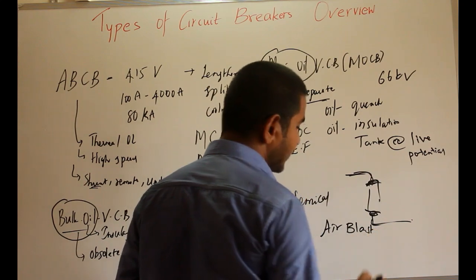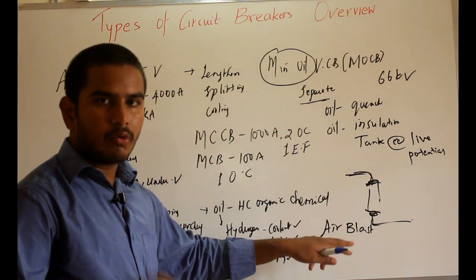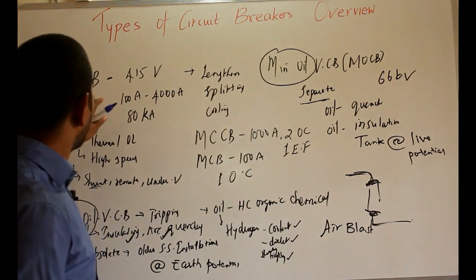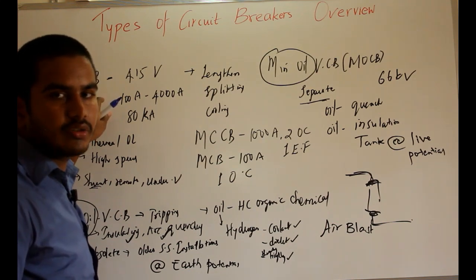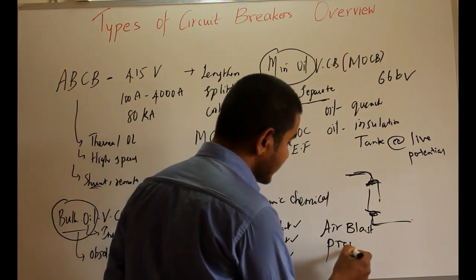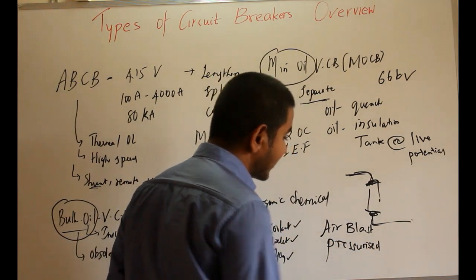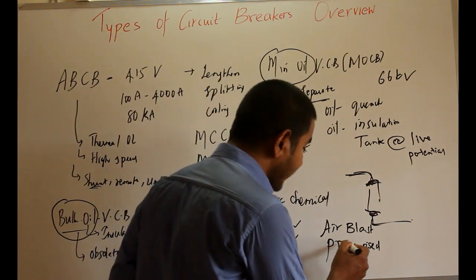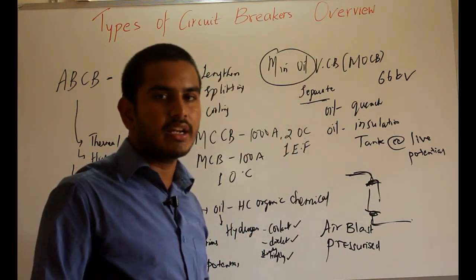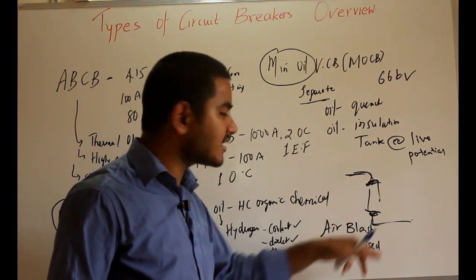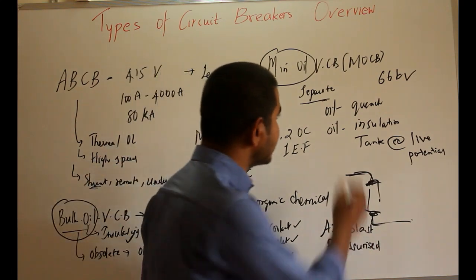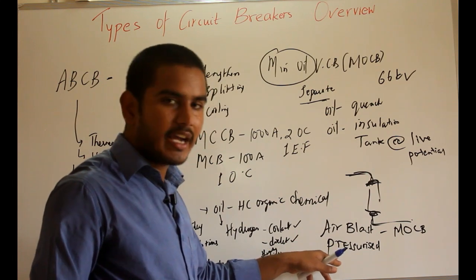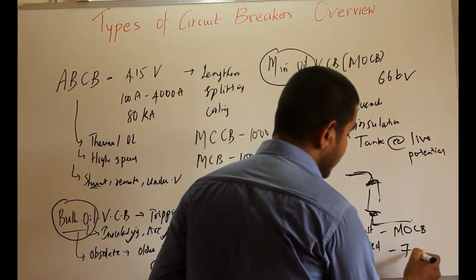Coming to the air blast circuit breaker: blasting or forcing the air under pressure increases its dielectric strength several times more than normal air at normal temperature and pressure. This fact, coupled with arc extinction using forced air, has made this air blast circuit breaker very popular, and it started replacing the minimum oil circuit breaker. As this pressurized air has high dielectric strength, it can be used up to 735 kV voltages.